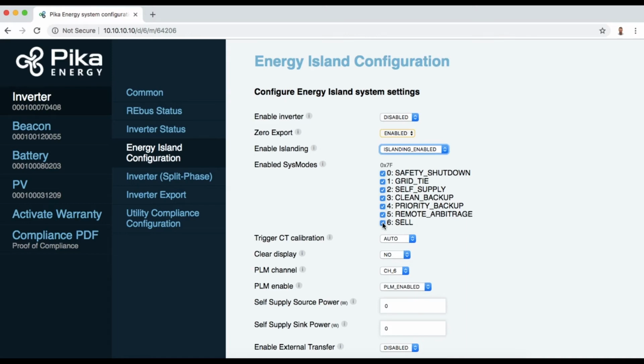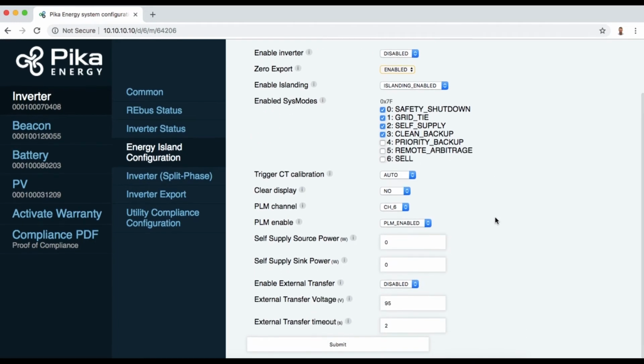So let's say hypothetically the utility does not allow this customer to sell power from the battery, do remote arbitrage, or charge the battery from the grid, which is what priority backup is used for. I would deselect those options. Another thing that I can do from the Beacon Installer tool is change my PLM channels. This is only relevant if you have multiple inverters installed at a single site.